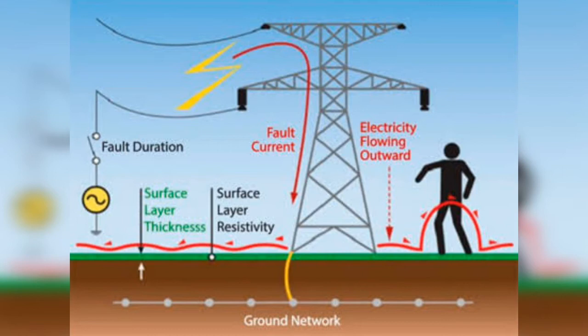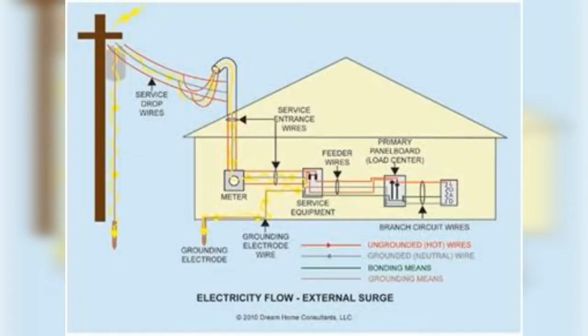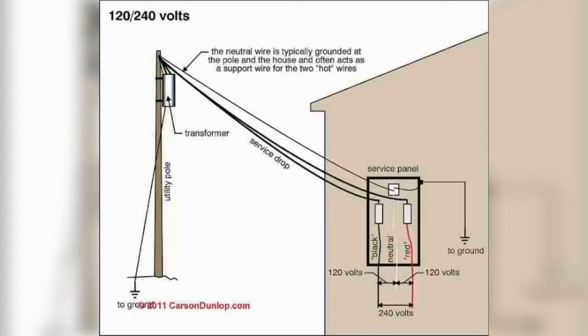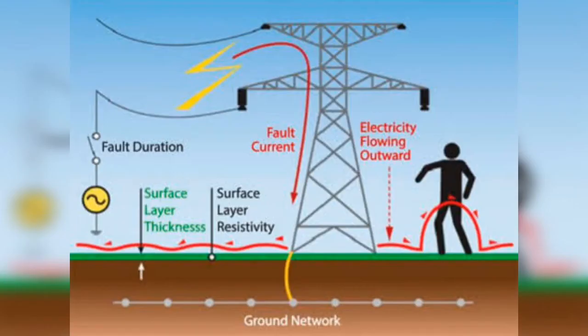Why does current flow to the ground? The reason current flows to the ground is because the neutral point of the supply transformer is connected via a ground conductor to the ground electrode. During a fault, or if someone touches a live conductor, the potential of the hot conductor rises to about 120 volts with respect to the ground surface, and current flows through the ground back to the transformer.